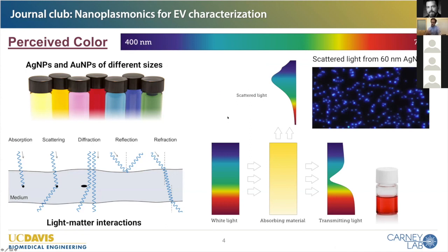But for scattering, it's the opposite. You actually are seeing the apparent scattered light color, the true color. And we typically collect it off to the side because scattering is happening, it's shooting out at every angle, it's random. And so if we want to differentiate that from the transmitted light, we pick it off at a different angle. And this is how flow cytometers work and lots of different NTAs and all of these different machines that use the scattered light that we're familiar with.